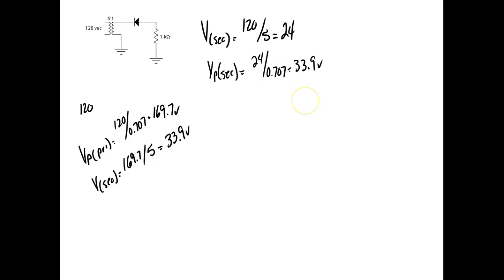Still no sign out here. This is still AC, so there's no such thing as negative AC and positive AC. AC has no sign. People get tied up on that black lead on their meter. They think in an AC circuit that black lead has to be connected to common. That's false. Y'all understand that? So in an AC circuit, the colors of your leads mean nothing. But you need to get used to putting the black lead in common and the red lead where you're trying to measure, because if you start swapping that around, it could give you problems later on. But in AC, when you make your measurements, the color of your lead makes no difference. So you could use red on common and black to measure in the circuit. You can swap those around and you get exactly the same thing.